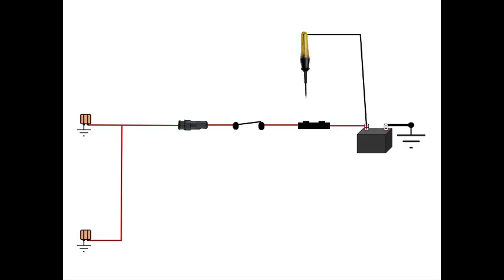Now what we are going to do is set up a test light to look for ground. We will begin by placing the test light's probe tip carefully into the output terminal of the fuse socket. We do not want to force this terminal open. Doing so will cause problems for future fuses. If the circuit was working properly, the light never would have illuminated. This confirms that we have an active short.